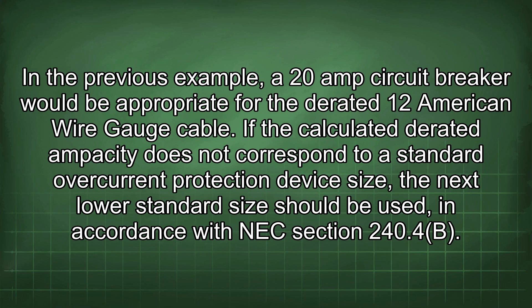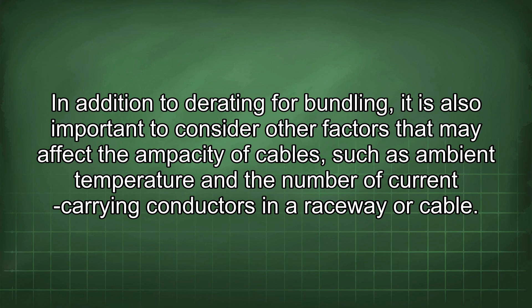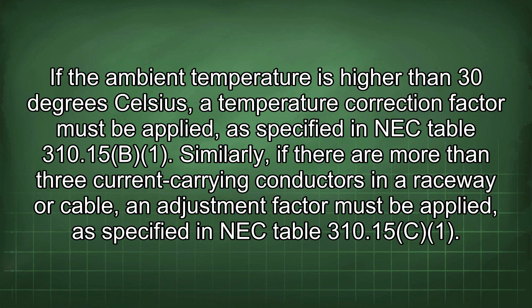In addition to derating for bundling, it is also important to consider other factors that may affect the ampacity of cables, such as ambient temperature and the number of current carrying conductors in a raceway or cable. If the ambient temperature is higher than 30 degrees Celsius, a temperature correction factor must be applied, as specified in NEC Table 310.15(B)(1). Similarly, if there are more than 3 current carrying conductors in a raceway or cable, an adjustment factor must be applied, as specified in NEC Table 310.15(C)(1). These adjustment factors further reduce the allowable ampacity of the cables to prevent overheating.